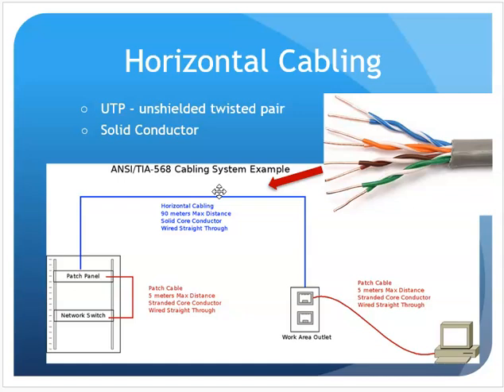But the benefit is this carries your signal a lot better, with a lot less signal loss and a lot less resistance with this solid conductor as opposed to that stranded conductor we looked at earlier. So with the patch cables using stranded, I'm getting that flexibility, but I have to keep the distance short. With the horizontal cabling, I'm using the solid conductor. It can break if I bend it a whole bunch, so I install it and leave it alone, but I'm getting the benefit of carrying the signal stronger for a longer distance.